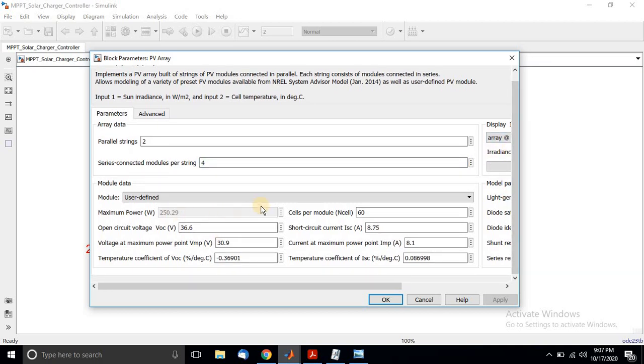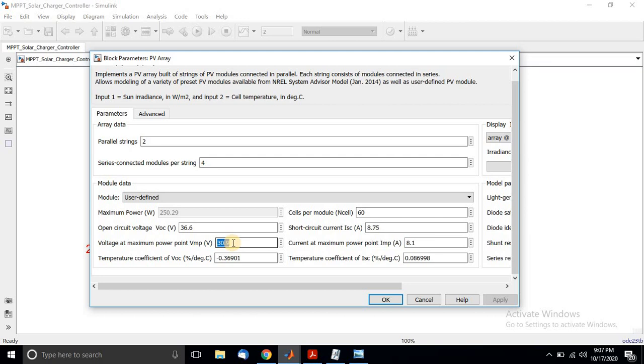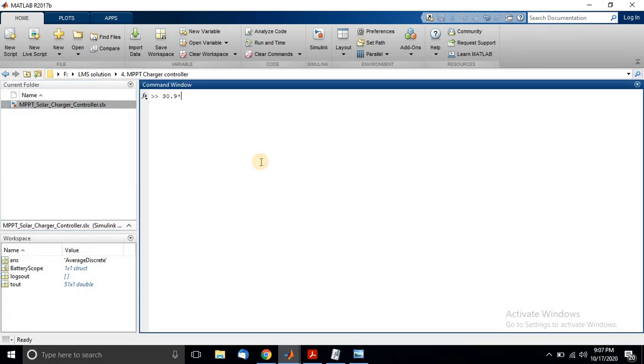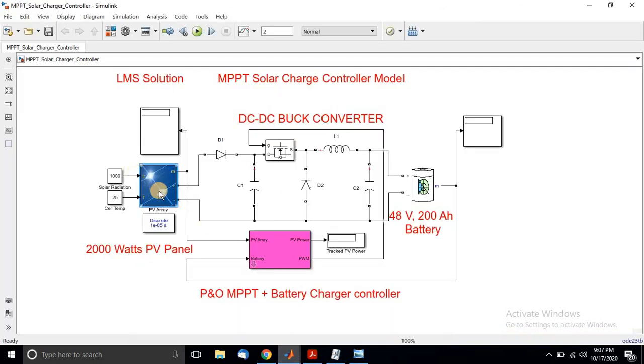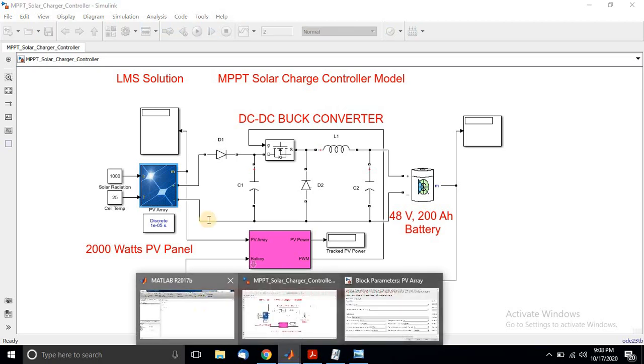This is the PV array details. The maximum power is 250 watts per module, maximum voltage is 30.9 V at maximum power point condition. With 4 series modules, the terminal voltage at maximum power point is 30.9 × 4 = 123.6 volts.